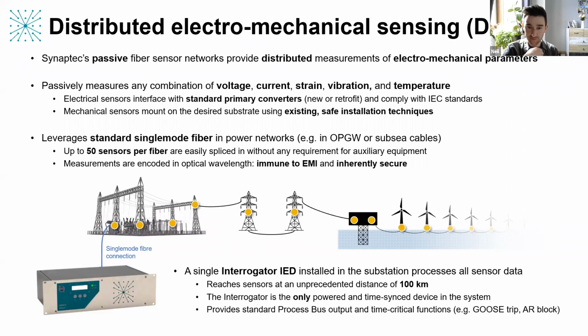So the sensors can be deployed over a very large area, and then at one end we have this single powered device, which is the interrogator. This will measure up to 50 sensors per fibre over a distance of up to 100 kilometers nominal distance from the interrogator to the final sensor in that array. And as I've said, this is the only powered and time synchronized device in the system, and typically those will be available anyway in the substation.